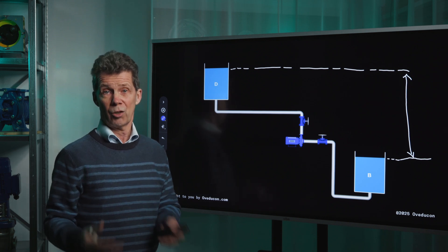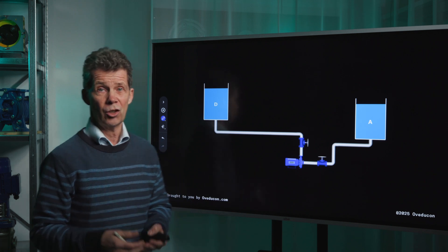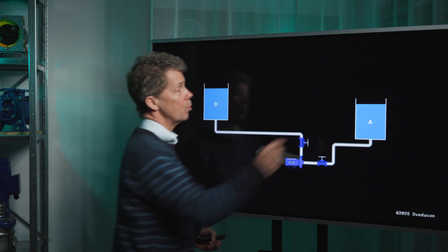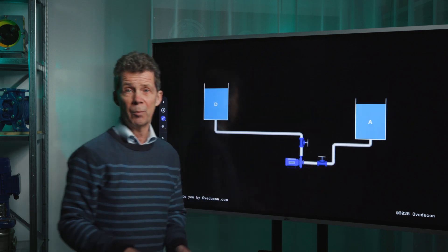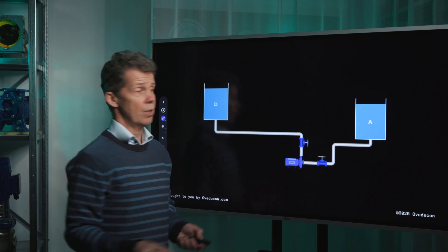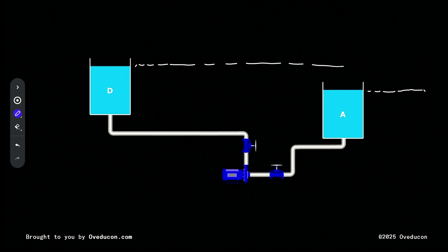We have another example for you. In this case we see a suction head situation. It is called suction head because the medium level is above the eye of the impeller. But the procedure stays the same — we draw a line from the medium level in the suction tank and the medium level in the discharge tank, and this distance is called the static head.